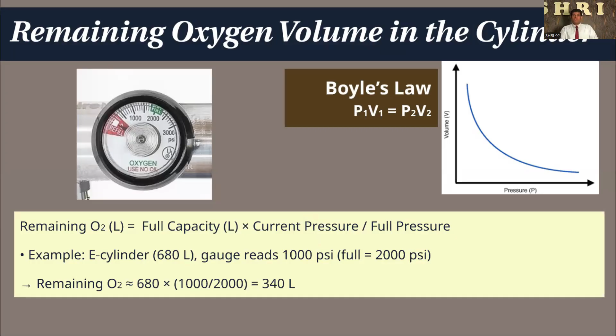So if we use an F cylinder, which is 1360 liters, and the pressure is 800 PSI, the remaining amount is 1360 times 800 divided by 2000. Likewise, you can easily calculate the oxygen remaining in a half-filled cylinder, because we can't always ask for a full cylinder; it is not practical.